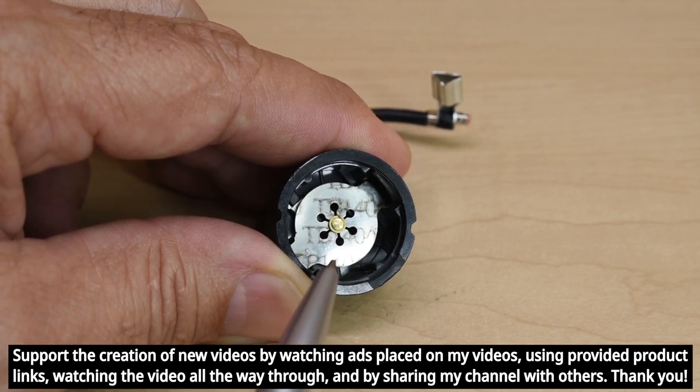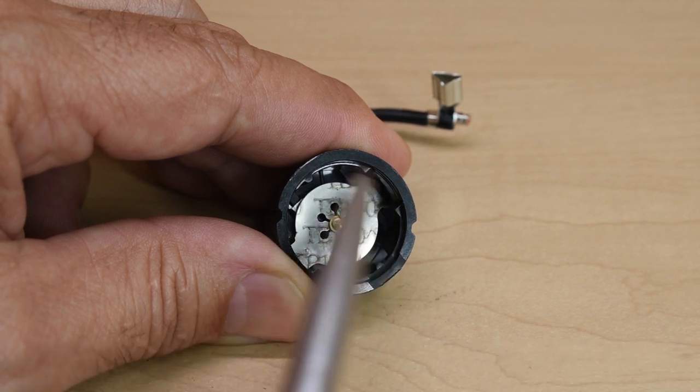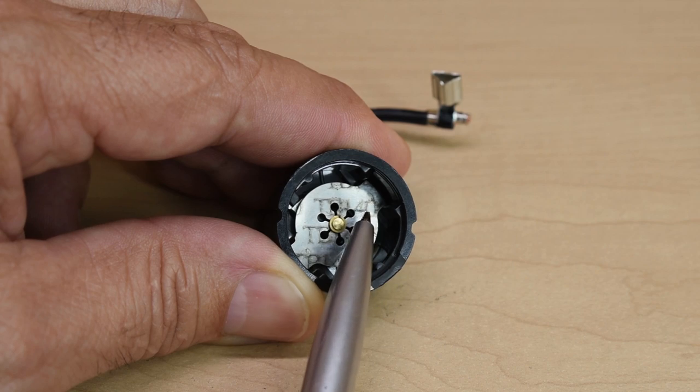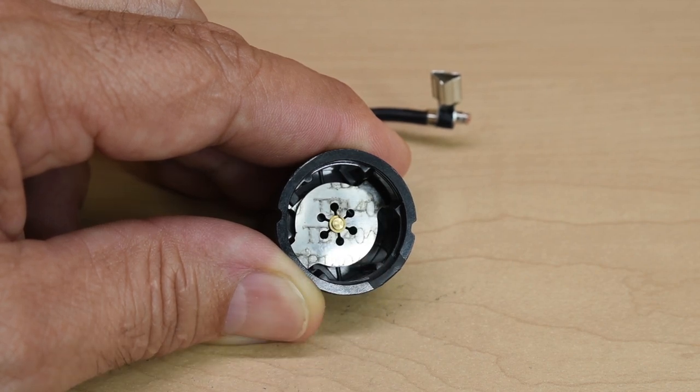To demonstrate, I'm going to take my heat gun. We're going to heat up the face of this overload protector, and you're going to see when this gets hot enough it's going to pop in the opposite direction.